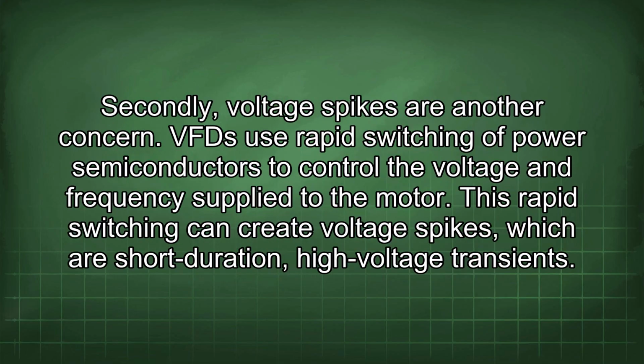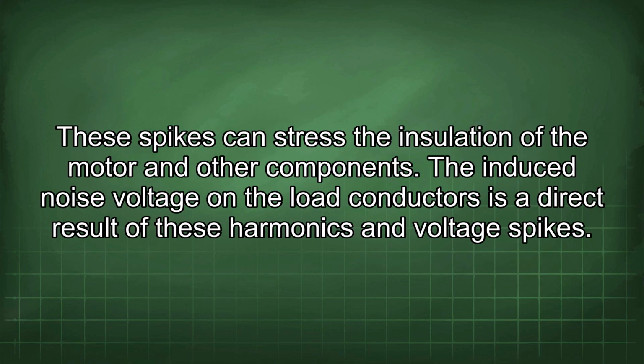Secondly, voltage spikes are another concern. VFDs use rapid switching of power semiconductors to control the voltage and frequency supplied to the motor. This rapid switching can create voltage spikes, which are short-duration, high-voltage transients. These spikes can stress the insulation of the motor and other components.